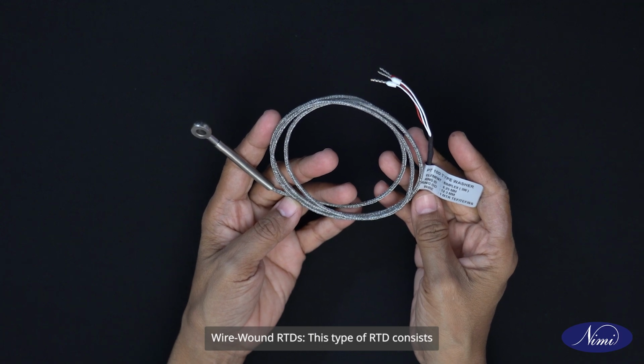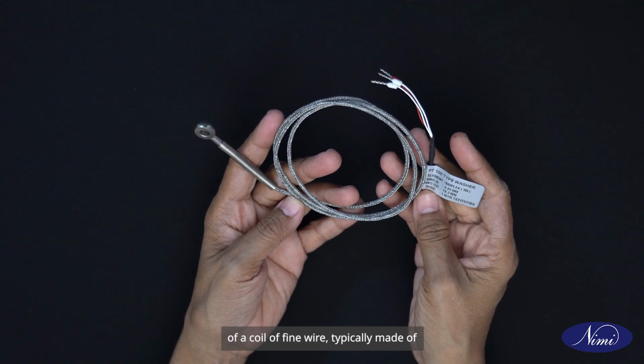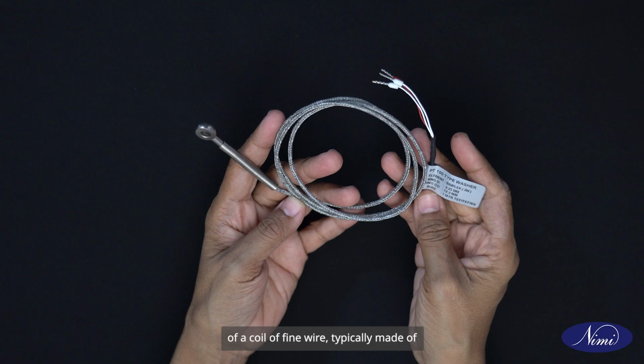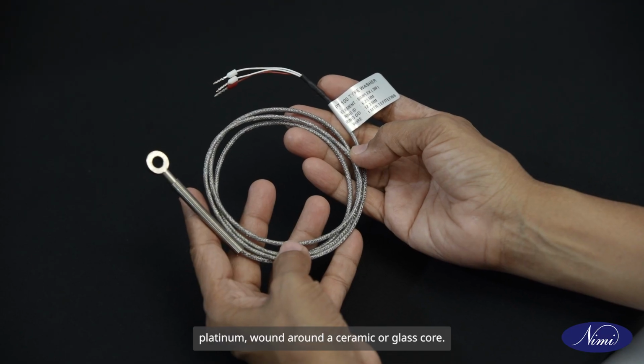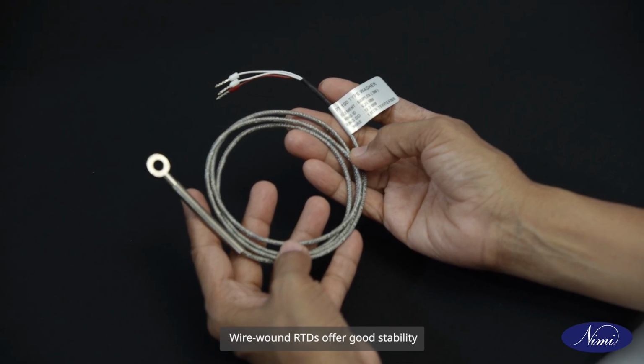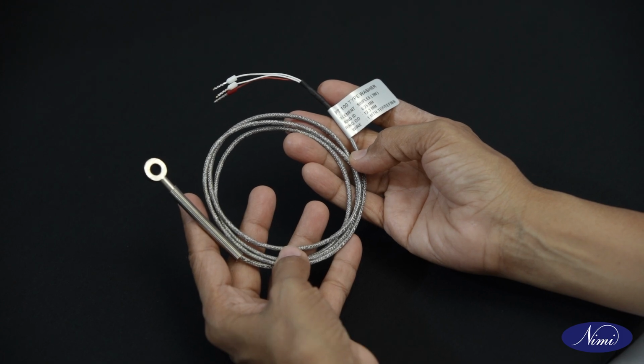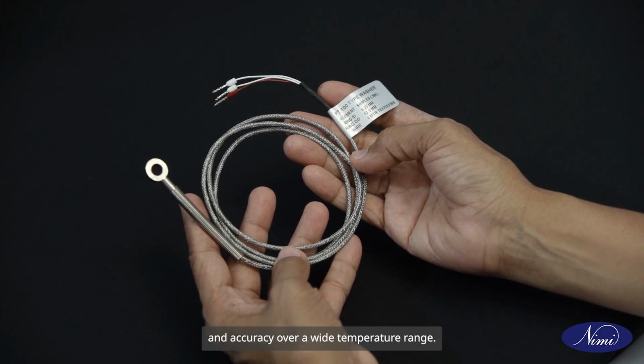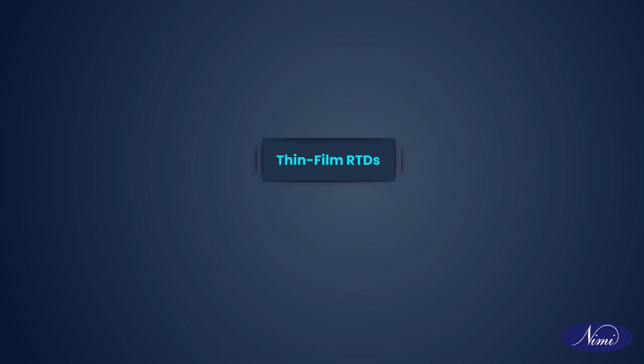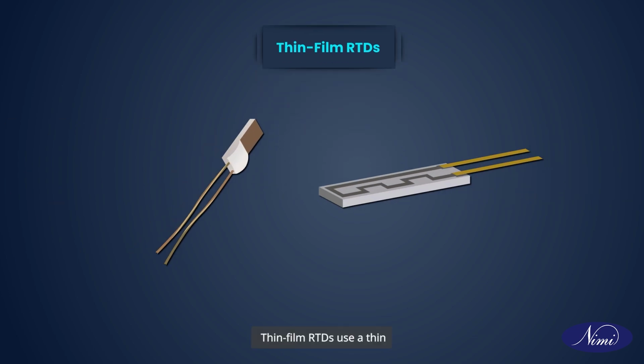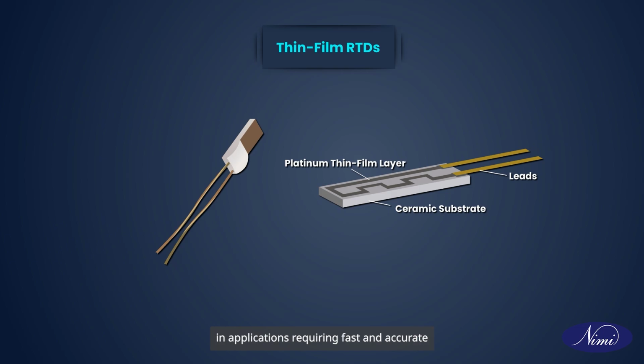Wire wound RTDs. This type of RTD consists of a coil of fine wire, typically made of platinum, wound around a ceramic or glass core. Wire wound RTDs offer good stability and accuracy over a wide temperature range. Thin film RTDs. Thin film RTDs use a thin layer of resistive material, usually platinum, deposited onto a ceramic substrate. Thin film RTDs are commonly used in applications requiring fast and accurate temperature measurement.